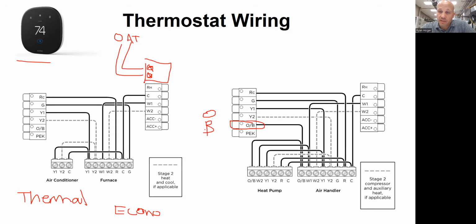Further on that, if you want to do the dual fuel thing, where you have the ability to run the heat pump or another heat source that's not electric resistance heat. So heat pump with a gas-fired furnace, heat pump with a hot water coil, heat pump with a steam coil. Any of those three examples, if you're doing one of those three, you need a thermostat that can support dual fuel.